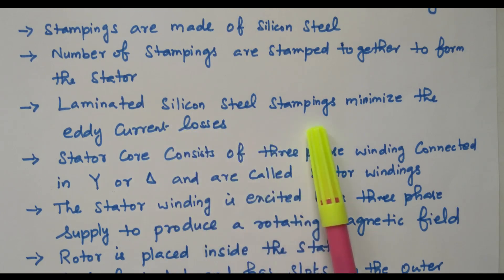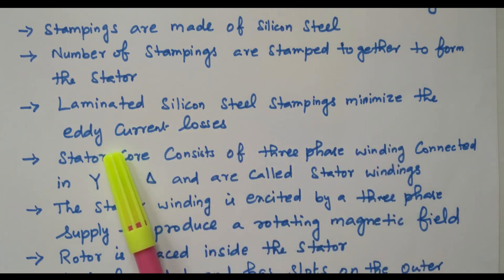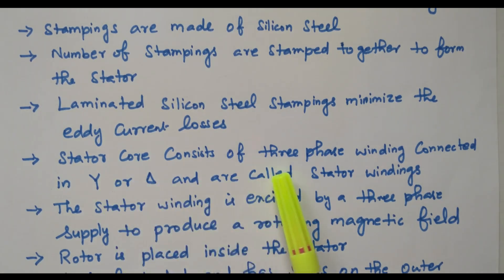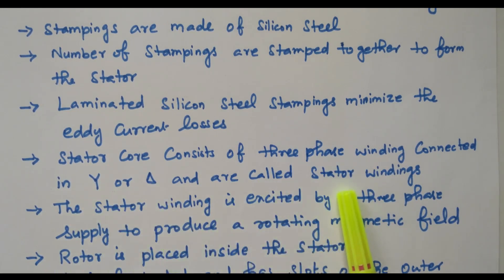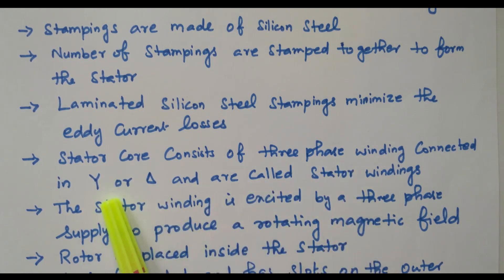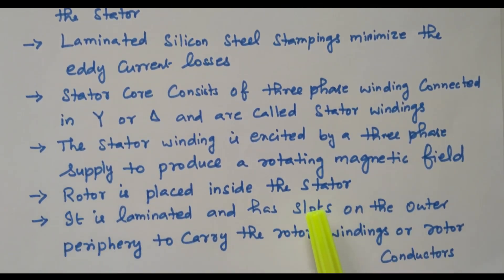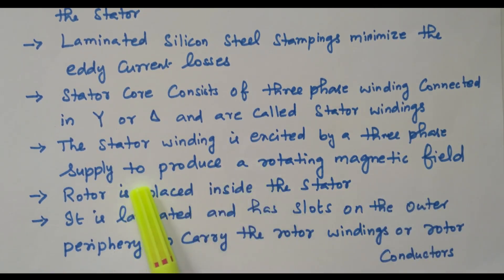Laminated silicon steel stampings minimize eddy current loss — that is the reason we go for lamination and stamping. The stator core consists of a three-phase winding connected in either star or delta, called the stator winding. This stator winding is excited by the three-phase supply to produce the rotating magnetic field.